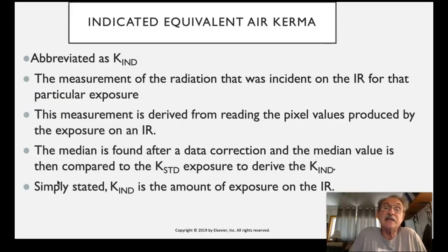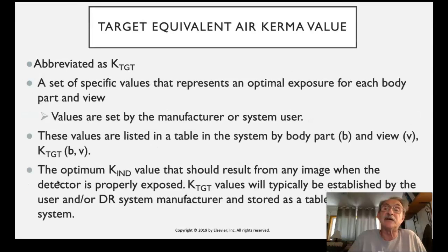Add to that the kerma indicated, which boils down to the bottom bullet point. Simply stated, the indicated air kerma is the amount of exposure on the image receptor. Okay, so this is the actual number that the system measures and reports out to us.